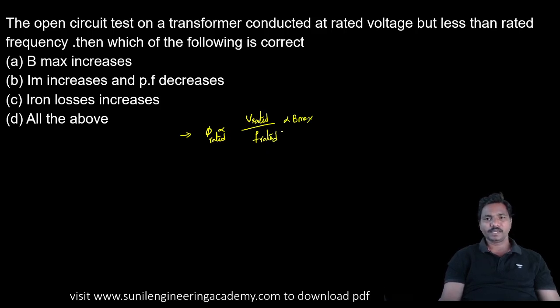So if the test is conducted at rated voltage but less than the rated frequency, as frequency is less, the Bmax requirement is more, Bmax increases, correct. As Bmax increases, the magnetizing current requirement increases. As I mu is more, what will happen to the power factor? It decreases. Power factor is always inversely proportional to I mu. So as I mu increases, power factor decreases, correct. Iron losses increase. As frequency decreases, what will happen to the iron losses here?